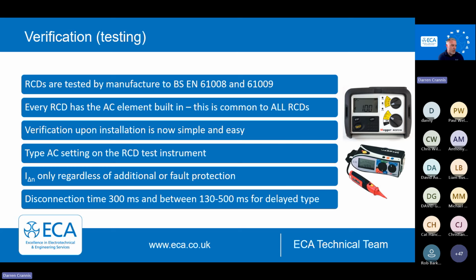Just remember that the old BS 4293 RCDs are effective if they disconnect in less than 200 milliseconds. And for time delayed, it's anywhere between 130 and 500. We only need to test on the type AC setting because that setting is built into every RCD. RCDs, by their product standard, are always tested in the factory before we receive them. We just need to do that quick verification test. So it's nice and simple. ×1 on the AC setting of your test instrument, and you're looking at typically below 300 milliseconds.